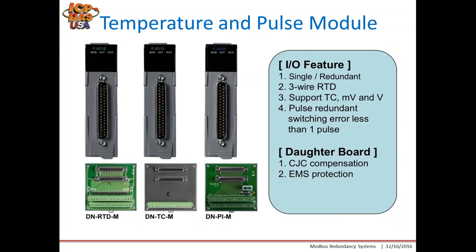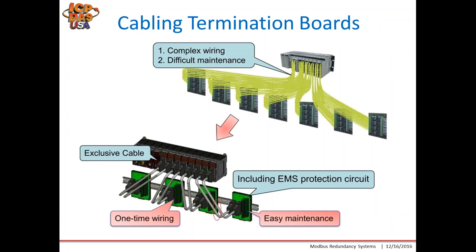For temperature and pulse modules, here are a few examples: the F8016, F8015, and F8084, which is our pulse module. The corresponding daughter boards are shown at the bottom. For cabling and termination, this example shows how everything is interconnected to the slot IO modules. Wiring can be very complex if you use terminal blocks where everything is connected. Our system incorporates DB cables, which is much neater — you wire all your sensors to the daughter boards for one-time wiring and easy maintenance.